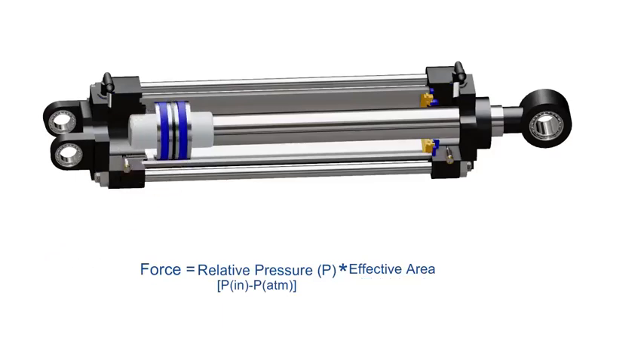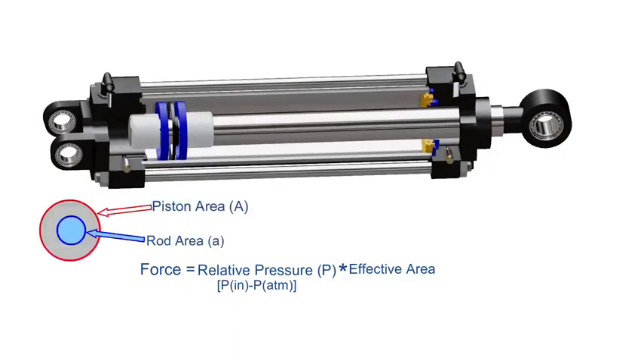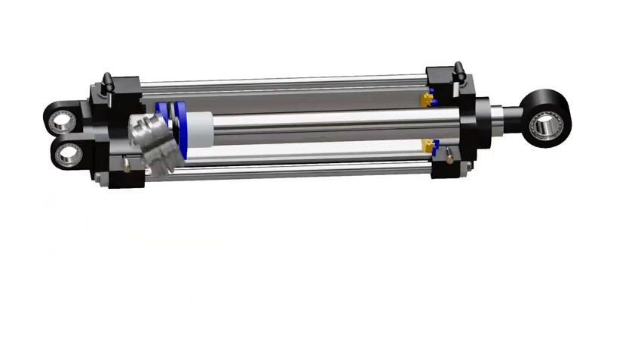During retraction, the effective area of the piston is reduced because air cannot exert pressure on the area of the rod. This gives us the theoretical force as relative pressure multiplied by the partial area of the piston. Frictional losses at the interface of different surfaces also need to be considered when designing a pneumatic cylinder. The diameter of the rod and the length of the stroke are also determining factors for the capacity of the actuator.